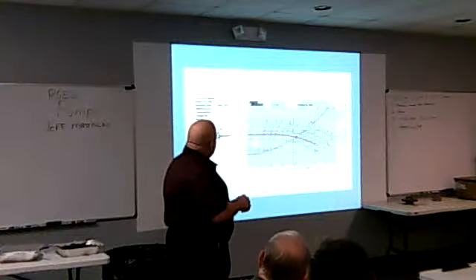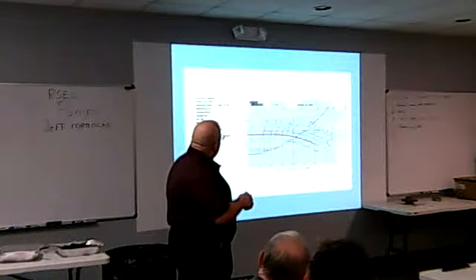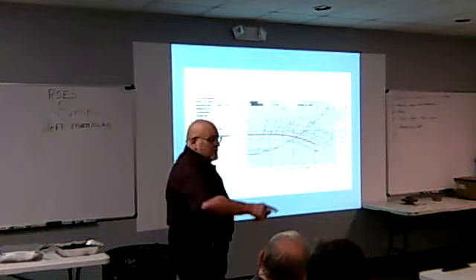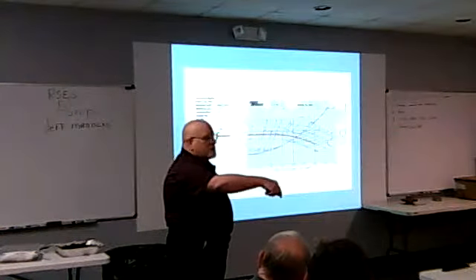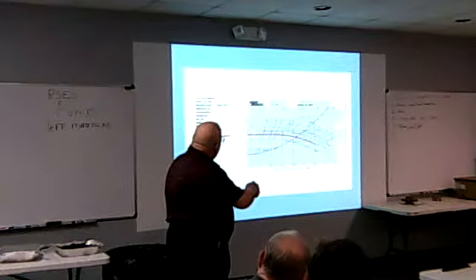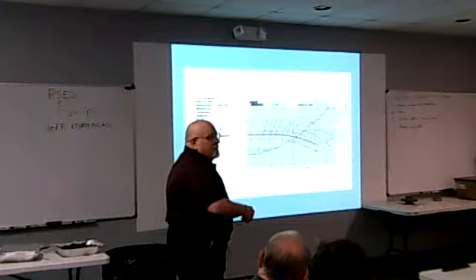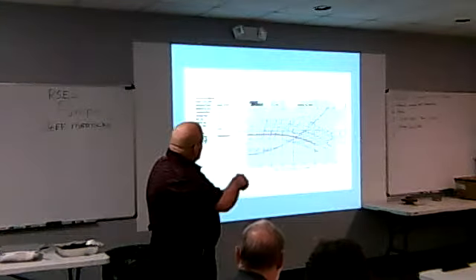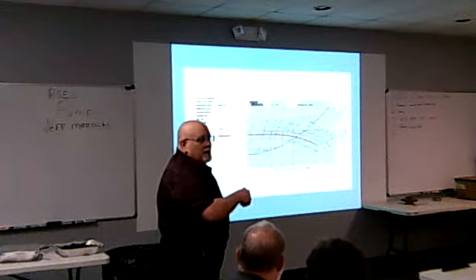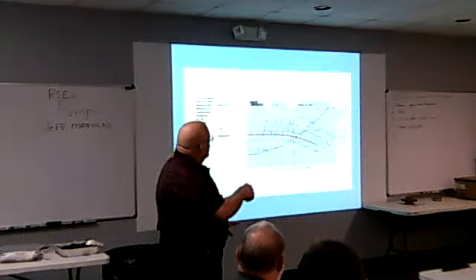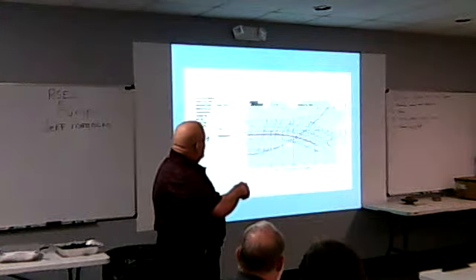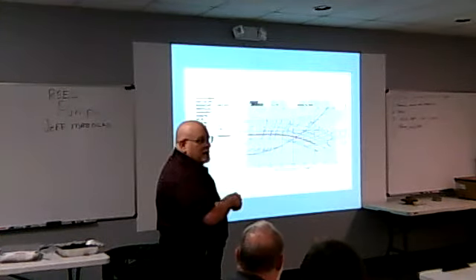These are your impeller cuts, these curvy lines going like this. Those are my impeller trims. Like that one there says 8.0 inches. The lower I trim this, the less head I can get out of the pump. But if I put this impeller, and we'll get to this in a minute, and I'm pumping down here, I'm pumping a lot of horsepower I don't need.